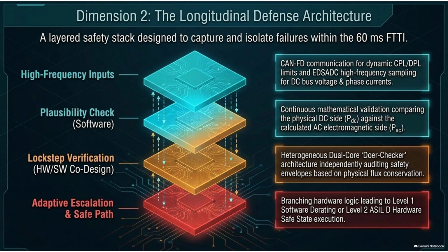It's called power plausibility diagnostics. Basically, if the data from the CAN bus can't be trusted due to noise or latency, the system has to cross-examine its own physical reality. It has to double-check the math. Exactly. It performs a continuous independent energy balance calculation. How does it do that? It calculates the physical DC power leaving the battery.